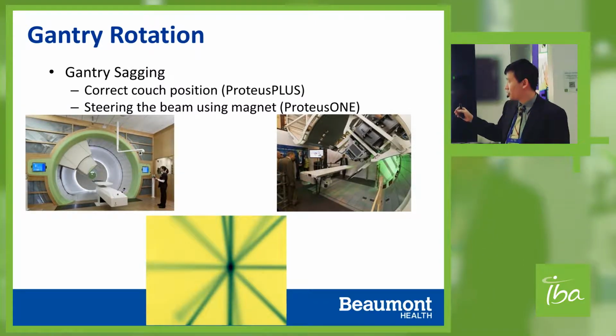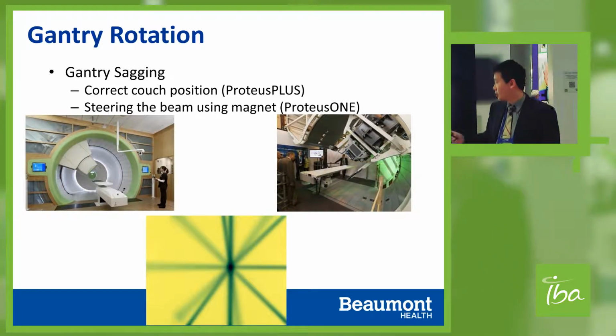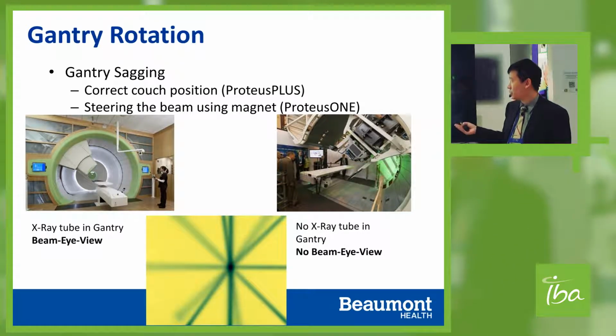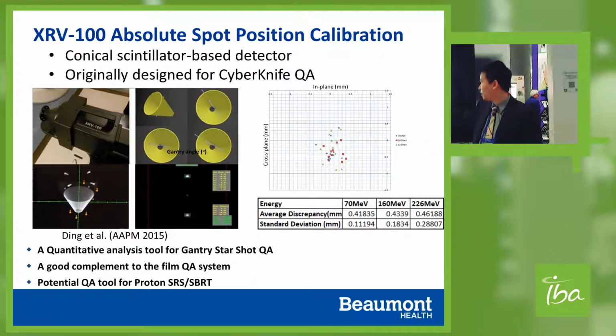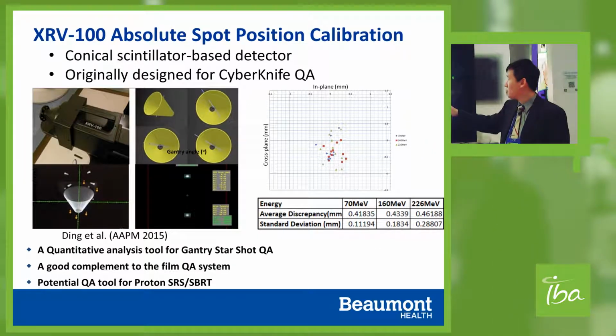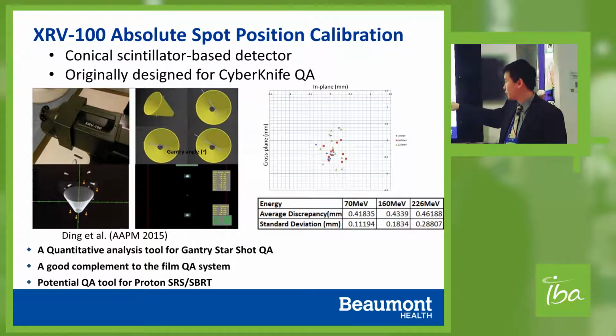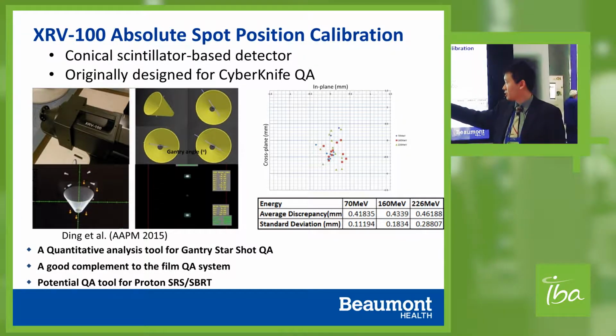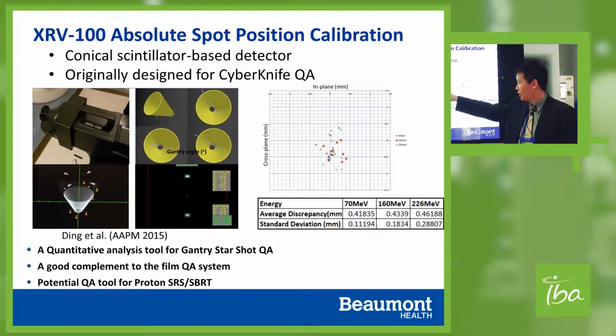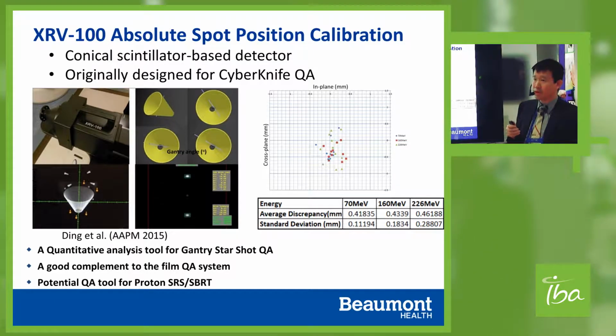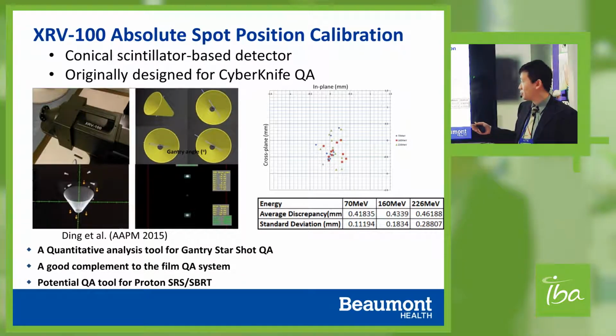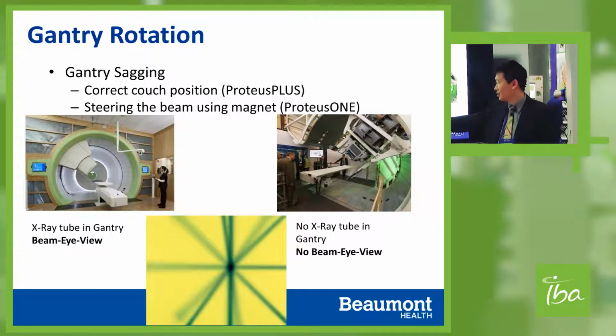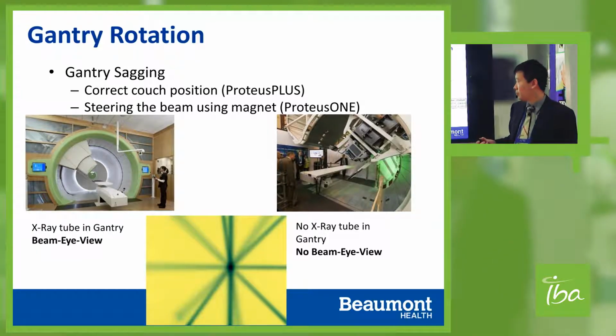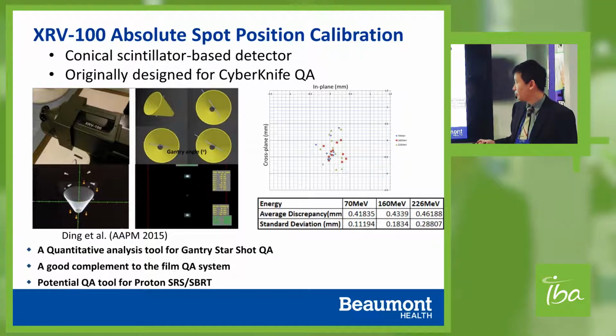To do the isocentricity check, we used film at the beginning, but the XRV 100 is really helpful to determine the isocentricity between different energy layers. So this is a study we published 2 years ago about the different energy selections, and we image with oblique imaging, crossfire for the XRV, put it at the isocenter, shoot the beam through different gantry angles, and also switch energy layers. That gives you very valuable and numerous data for your machine performance. Instead of using hundreds of films for the star shot as traditionally what we did, now we can finish that QA in about 30 minutes to an hour.